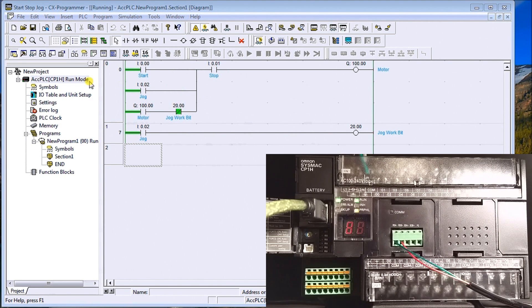The first thing to note is that our PLC is currently in Run mode. Run mode is for normal system operation — the operating status of the CPU unit can be monitored, but you cannot force or reset anything. Also, present values and set values cannot be modified using programming devices.